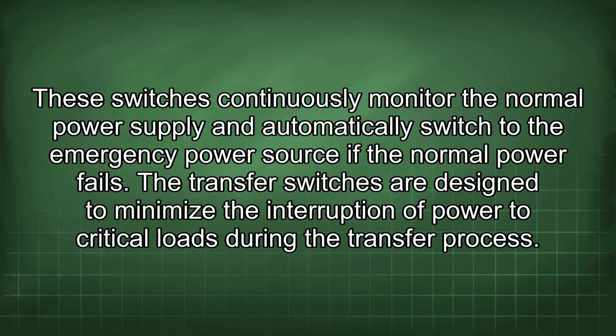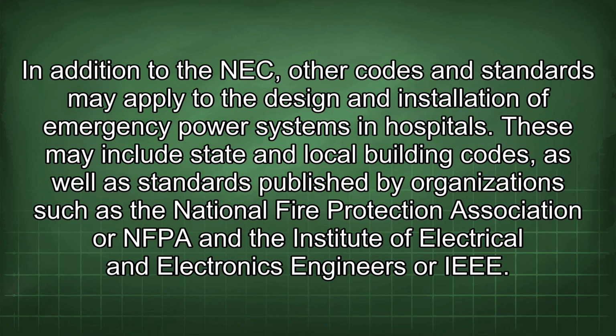These switches continuously monitor the normal power supply and automatically switch to the emergency power source if the normal power fails. The transfer switches are designed to minimize the interruption of power to critical loads during the transfer process. In addition to the NEC, other codes and standards may apply to the design and installation of emergency power systems in hospitals. These may include state and local building codes, as well as standards published by organizations such as the National Fire Protection Association, or NFPA, and the Institute of Electrical and Electronics Engineers, or IEEE.